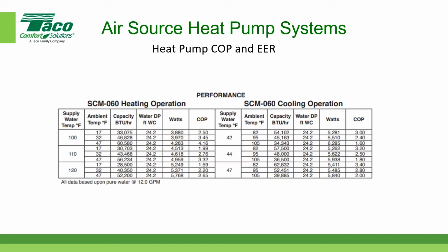Did he say minus 20 or 20? No, minus 20, yeah. I do know that the CO2 refrigerant-based units can produce a higher temperature water and get a COP above 1 at relatively low temperatures, but I don't know exactly what those are. I don't think there's that much in the way of published data yet for that equipment. So the answer would be I'm not aware of one, but some manufacturers are getting close to those kinds of values, and I would expect in the next year or so, probably less than a couple of years, we should start to see some manufacturers publishing that kind of data. Any other questions, Brent?